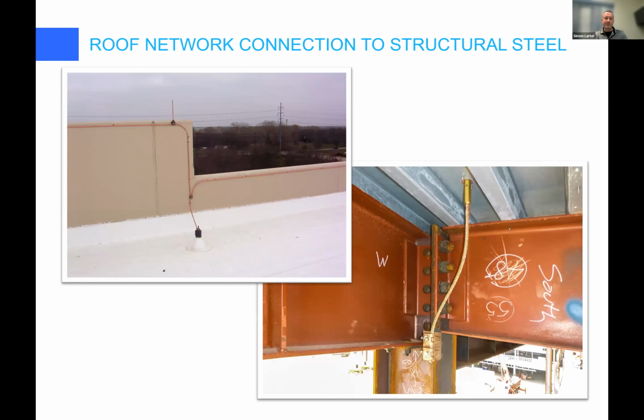Here we go with the connections to structural steel. You can see there on the left-hand side, that's our through roof connection. The roofer puts his waterproofing boot over it. You can see again, we've got those nice gentle sweeps. Then the conductor comes in, connects up to the through roof connection, and there underneath, we're connected up to steel. At that point, the steel can carry the charge down to ground.